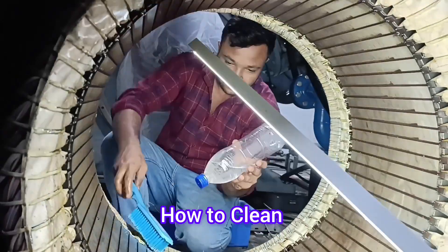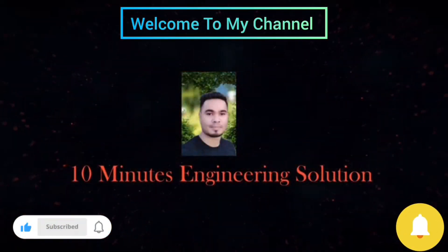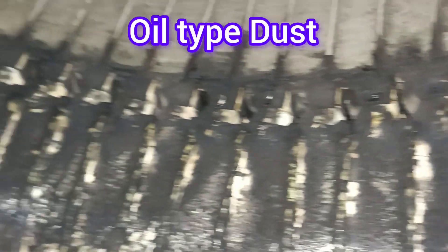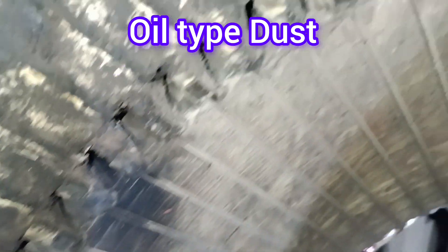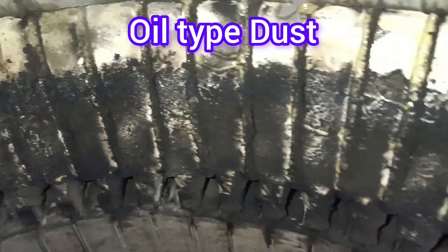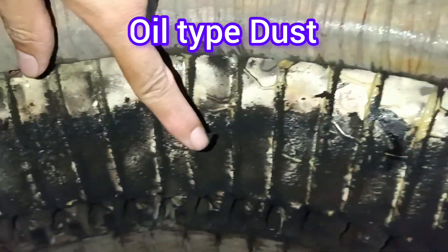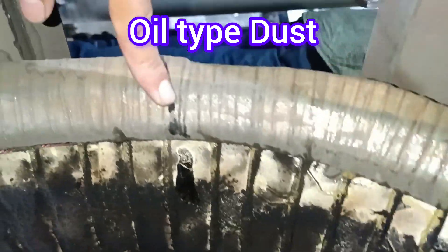First of all we need to clean the motor. This is 10 Minute Engineering Solutions. You can see oil-type dust here — lots of oil-type dust accumulated inside the motor. That's why the motor is failing. Due to lots of moisture carrying the dust and making it oil-type, the coil contacts with the dust and ultimately a spark happened. This is the sparking spot.